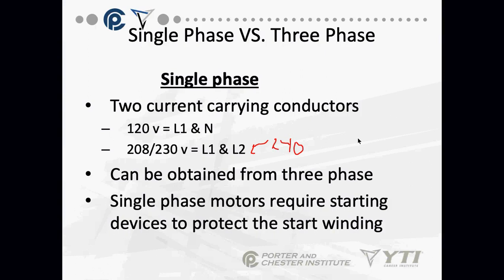Okay. Single phase, I can obtain it from a 3-phase circuit. We do this in commercial buildings all the time, including your campus building. We do this all the time. Okay, if I have L1, L2, and L3, I can use L1 and L2 by themselves. And with a little bit of magic, I have single-phase current. I can create a neutral. Okay, and you have single-phase current. Okay, if I create a ground and go L1 to ground, I can have single-phase. That's way oversimplified. But I can create single-phase from a 3-phase circuit.